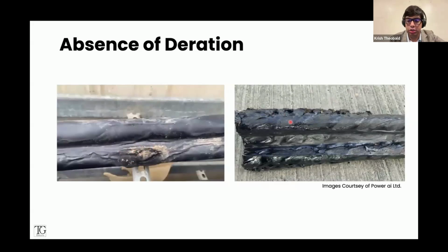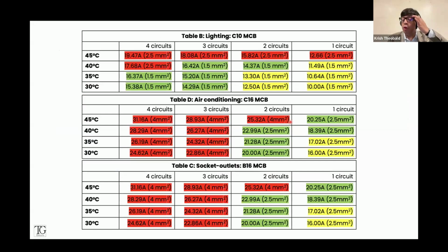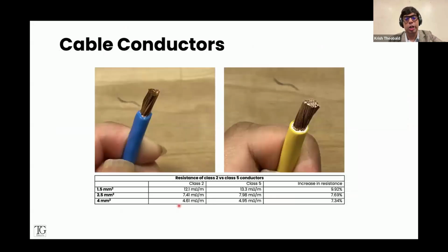complete degradation of insulation. We have a thumb rule in India sometimes where we say lighting, 10 ampere MCB, 1.5 square mm; air conditioning, 16 ampere MCB, 2.5 square mm; sockets, 2.5 square mm, 16 ampere. But if we consider the two main factors, which are grouping and ambient temperature, you see that in most cases the thumb rule does not actually work. So you need to actually size up much, much higher. Conductors as well, we've got our class 2 and class 5 conductors. We know that we have to use class 2 only in India.